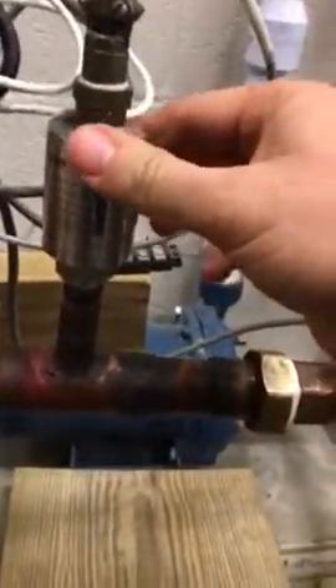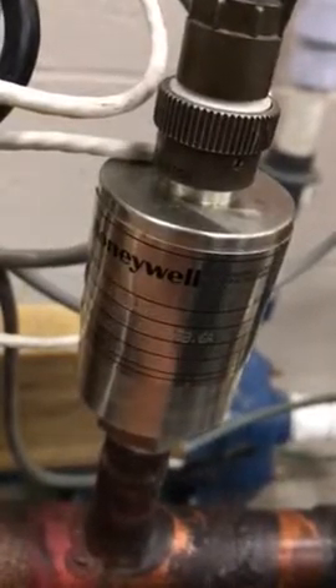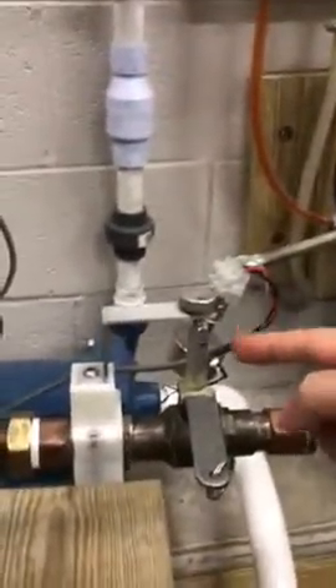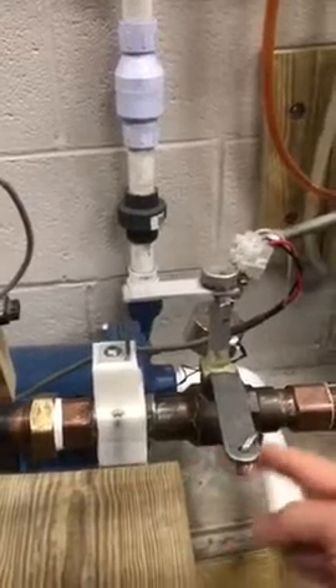First of all, I'm using these transducers. It's a Honeywell 200 psi, as you can see here, and the angular sensor is installed on the ball valve. This is the pipe I'm going to measure. It's about 160 meters in length. It goes up, as you can see, in loops to the upstairs, and upstairs there is a tank and another transducer just like this one installed there. And as you can see, this is the wiring coming from upstairs.